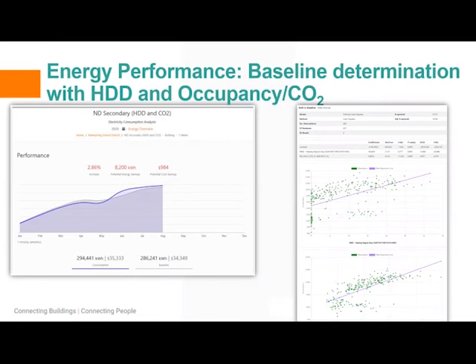Now, when the second independent variable, in this case CO2, was used, we found that the actual energy consumption in the building is higher than the baseline. In fact, the actual consumption was 2.86% higher and close to $1,000 of excessive energy consumption was happening. Why this example? It's just to communicate that EIS is an important component in commissioning, number one. Number two, you also need to make sure with COVID-19 and a post-pandemic world we are entering, HDD and CDD, or heating degree days and cooling degree days, are no longer the only independent variables that we should be using. Of course, they're a big part of it, but we now are entering a world where occupancy in buildings is fluctuating all the time.